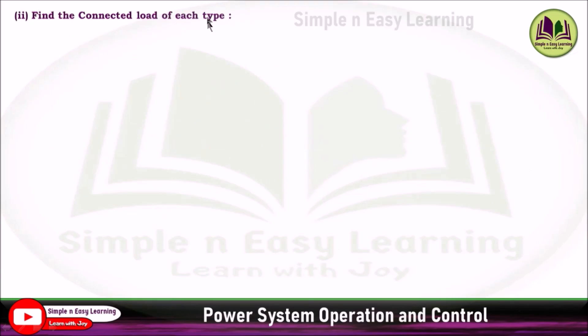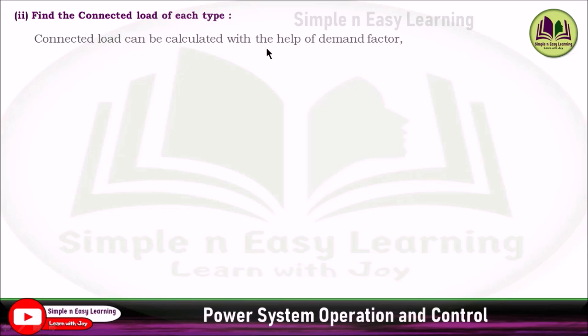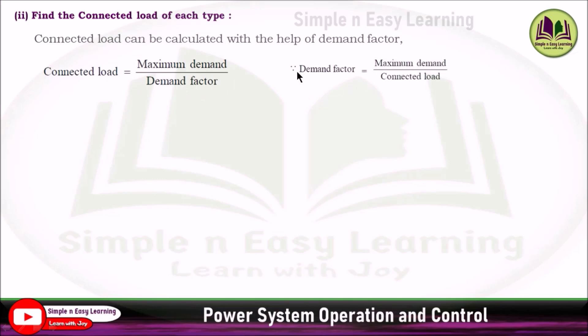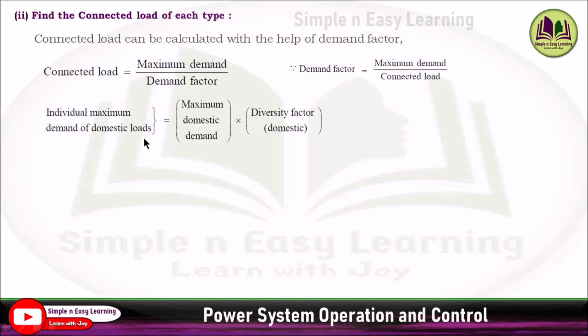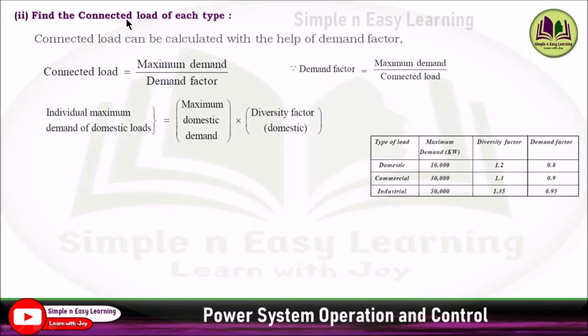Next, find the connected load of each type. There are three types: domestic, commercial, and industrial. The connected load can be calculated using the demand factor formula: connected load equals maximum demand divided by demand factor. As we know, demand factor equals maximum demand divided by connected load. The individual maximum demand of each type is calculated by multiplying the maximum demand by its respective diversity factor.